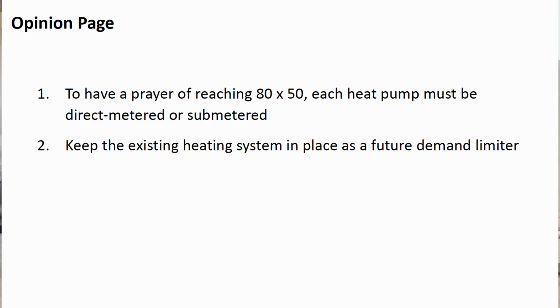This calculation includes the actual kWh used by each heat pump. We set up an instrumentation system so that we could get the individual kWh for each one of the heat pumps. So it's not an estimate, it's the actual usage. Offline I can show you that if you're interested.